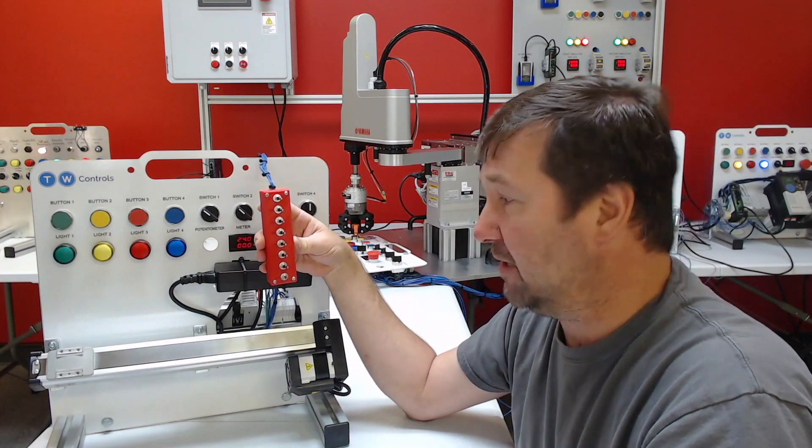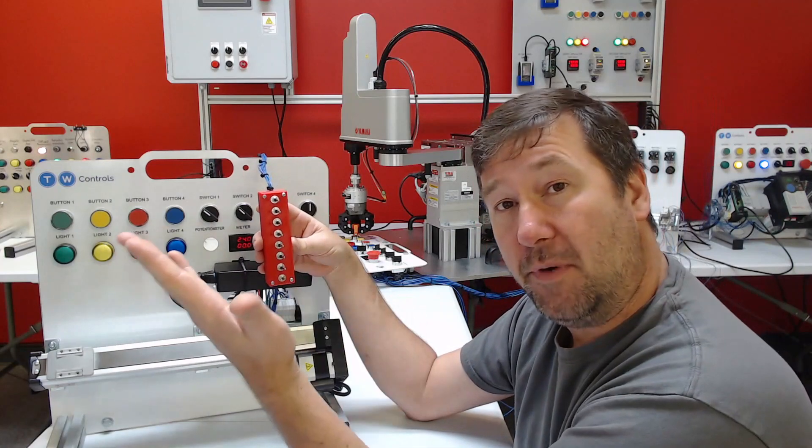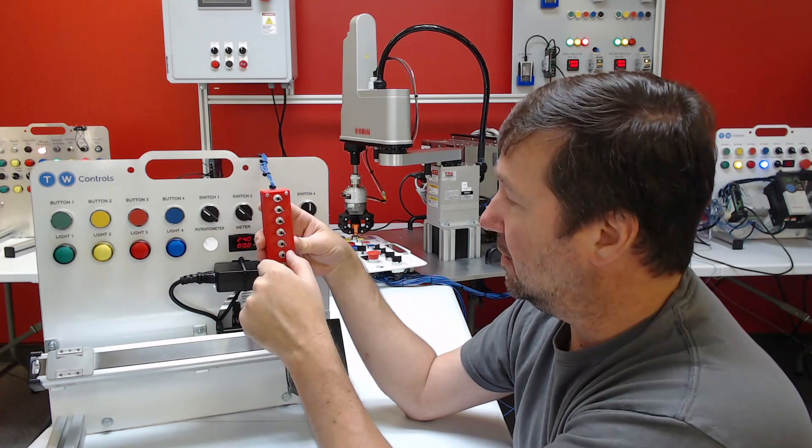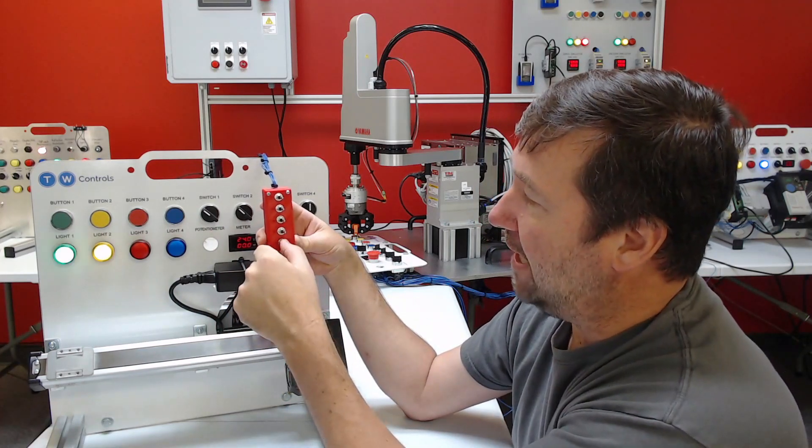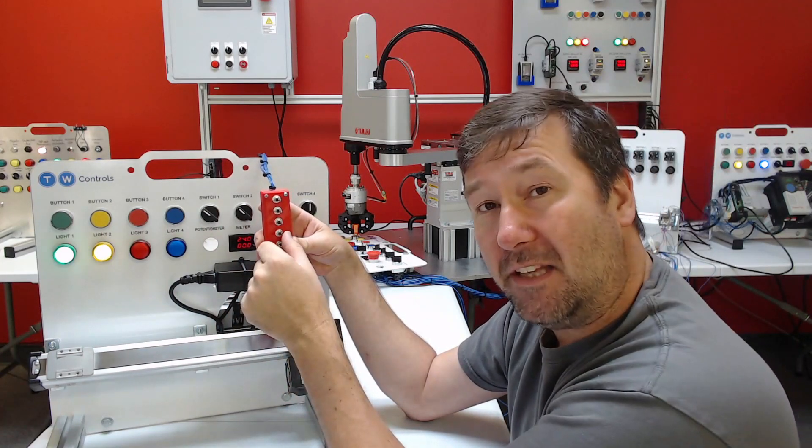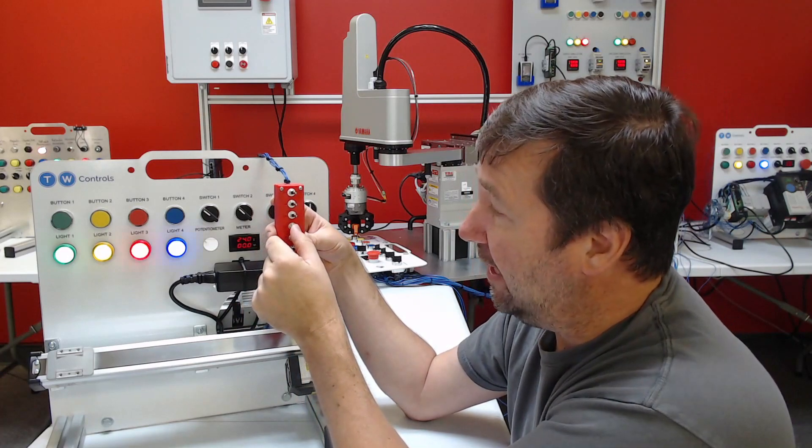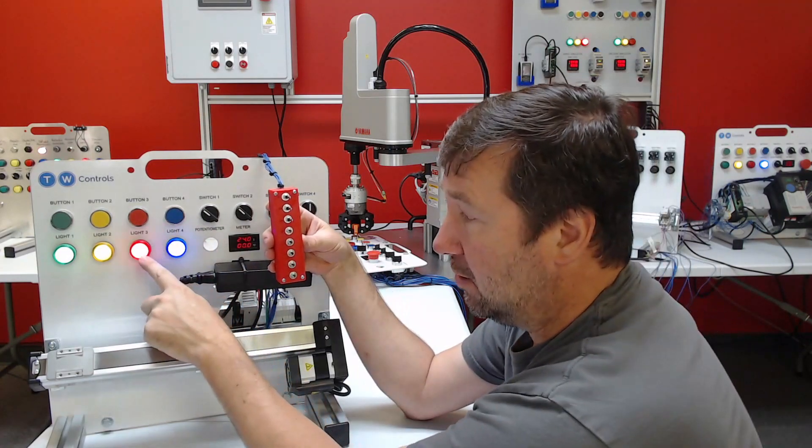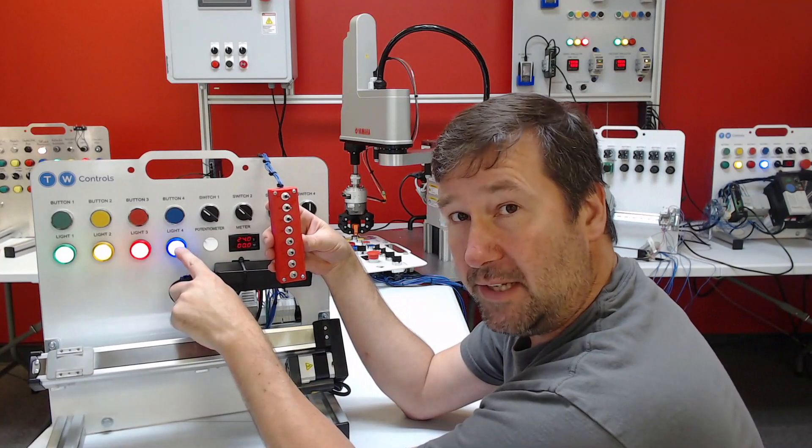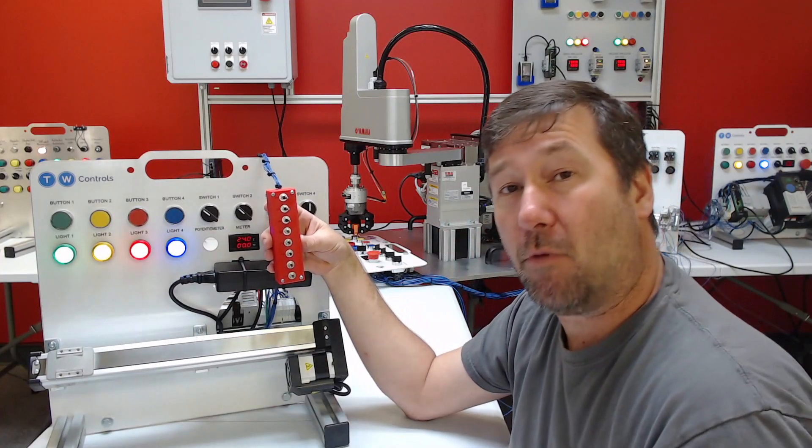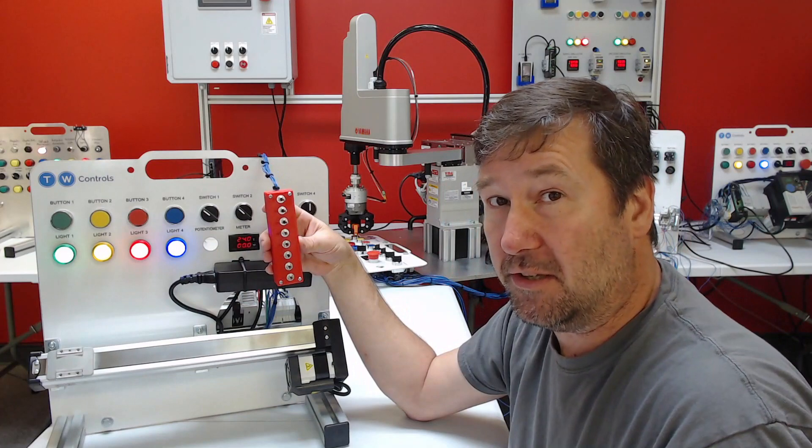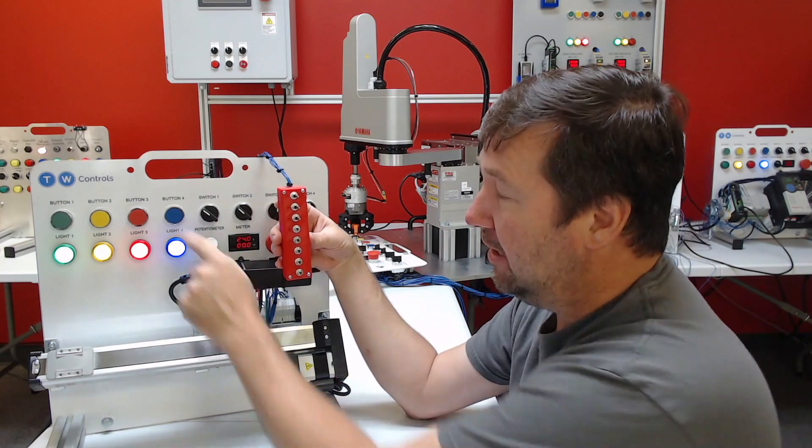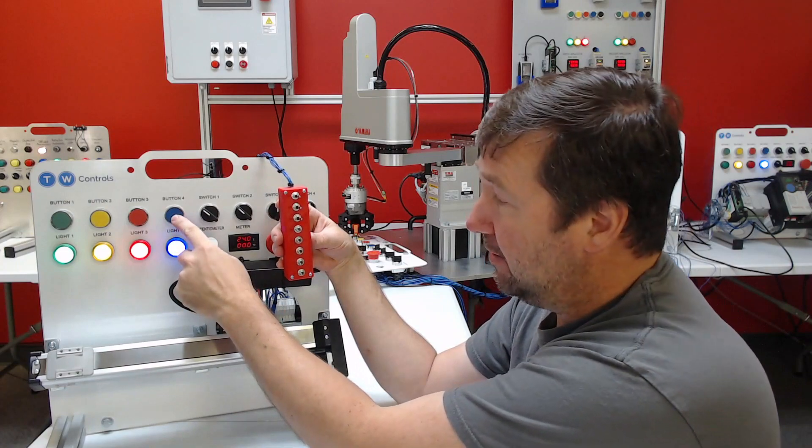All right now let's talk about our alarm conditions. First we can't keep up. So stop float comes up. Lead float comes up. Lag float comes up. And finally we have that high alarm float. And it comes up. So a couple things about it is first it does turn on our alarm light and our alarm buzzers. Well when you're there working on it you don't have to hear the buzzer working all the time. Because that's how we end up with buzzers getting unwired. So we need a silence. And I've set the blue button up here as our silence. So I press it.